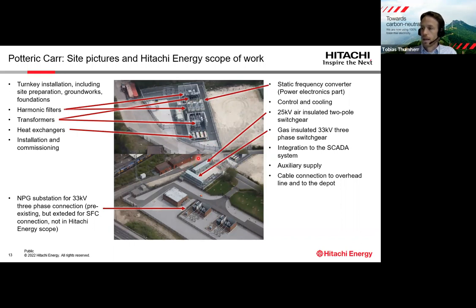So we have the substation here for the SFC with 25 kV air insulated 2-pole switchgear that is containerized, as well as the 33 kV gas insulated 3-phase switchgear. Then we also had the integration to the SCADA system in our scope, the auxiliary supply, and the cable connection to the overhead line and to the depot. Also shown in this picture, and not included in the scope of Hitachi Energy, is an existing Northern Power Grid substation for 33 kV. That, as I said, was existing already, but was extended to allow this connection of the static frequency converter.